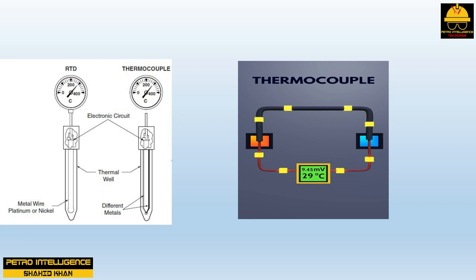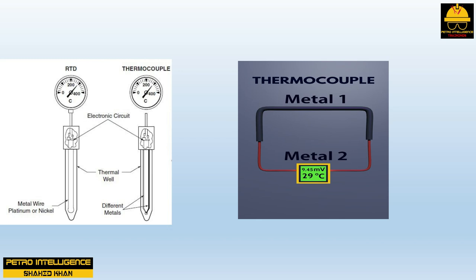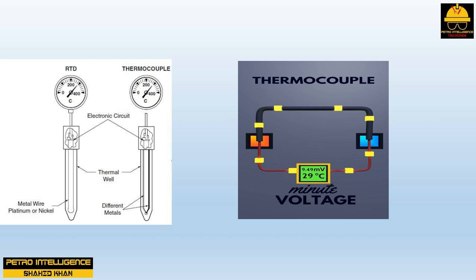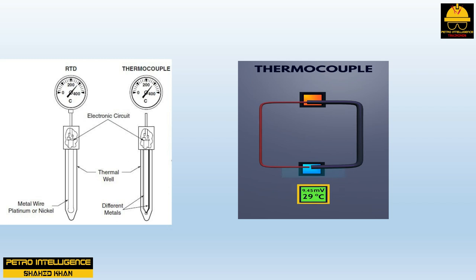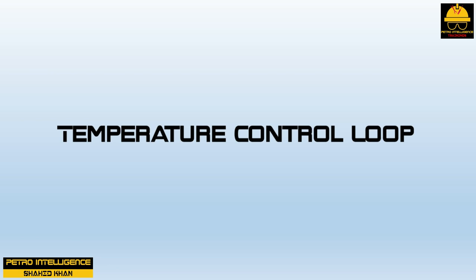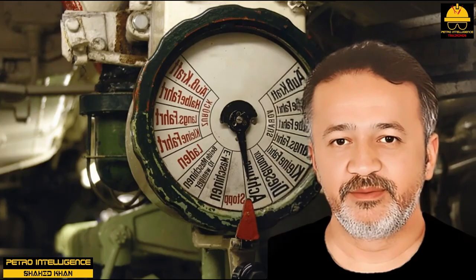Thermocouples are composed of two different types of metal and are designed to convert heat into electricity. When heat is applied to the connected ends, a low-level current is generated; the higher the temperature, the greater the current. Electric current is detected by the associated electronic circuit and converted to a corresponding temperature scale. Thermocouples come in several types; J-type and K-type are the most common, with K-type preferred for higher temperature measurements.